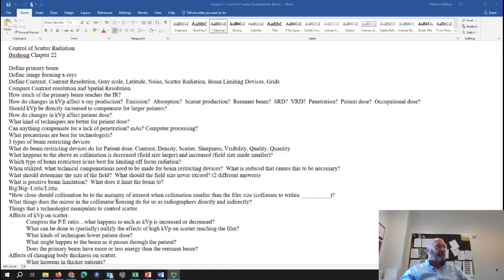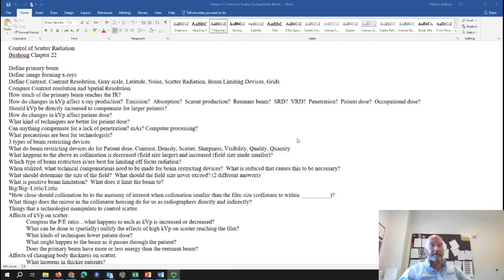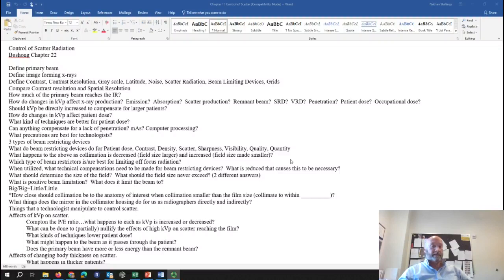How close should you collimate to the anatomy of interest when collimation is smaller than the film size? Collimate within half an inch to no more than an inch of the anatomy. The reason is the collimated field size is just the size of the projected light field. The light field and radiation field should line up perfectly, but there is acceptable variance — about 0.8 inches at a 40-inch SID. This ensures that if the collimators are slightly inaccurate and you collimate to just the size of the anatomy, there's some margin of safety.